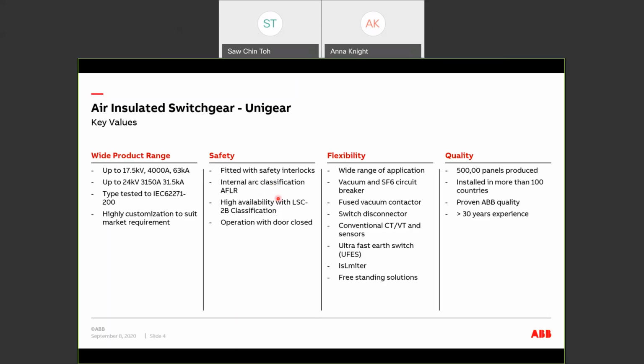Switchgear is also designed with high availability in mind. LSC2B classification means the switchboard can remain operable when one of the main circuit breaker compartment or the main compartment is opened. This is the highest availability based on the IEC standards. We, of course, continue to improve the product over the years. UniGear ZS1 can now accommodate a lot of types of switching technology to address different needs. We have designed to accommodate vacuum circuit breakers, SF6 circuit breakers, fuse contactors, switch disconnectors, and many more.